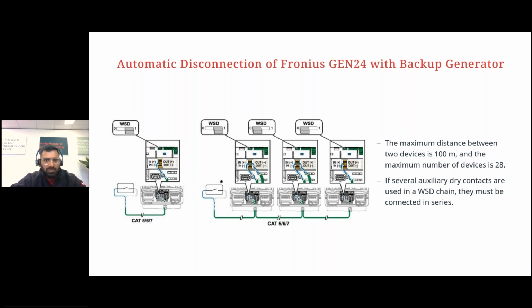Here you have a scenario where you may have multiple inverters that you need to put into standby. Again, this WSD is like a series connection. You have these dip switches that you need to take care of. Only on the first inverter it is on; on all the others it is set to off. Maximum distance between two devices is 100 meters, and you can control up to 28 devices using this WSD.